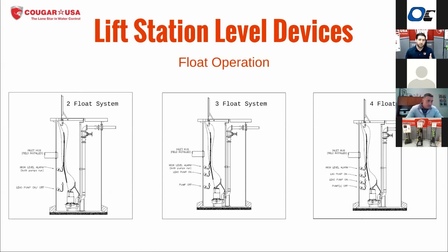So anytime you're doing a grinder station or shredder, something like that, you're going to want to use at least a three float system like this so that you can extend the pump down time for the grinder. Because a lot of times the way those grinders work is they start to pull things into the cutting wheel, chew on it for a little bit, spit it out, come back in, chew on it a little bit more, and then finally suck it in and out of the pit. And if you have a short pump down time, a lot of times the water will just be what gets out and you're left with a bunch of half chewed up trash in the pit. So you want to have that longer pumping range for the grinders so that you can get everything out of the pit.